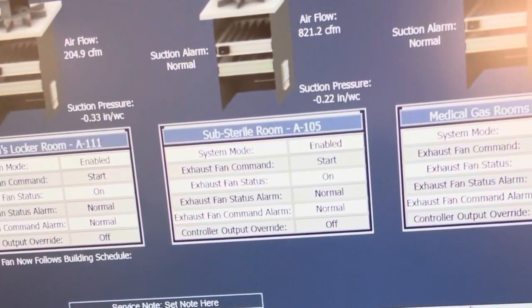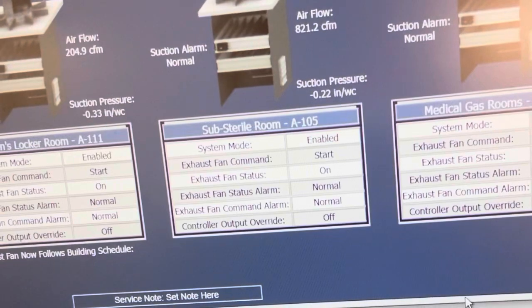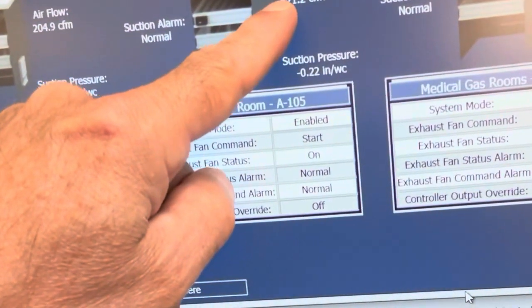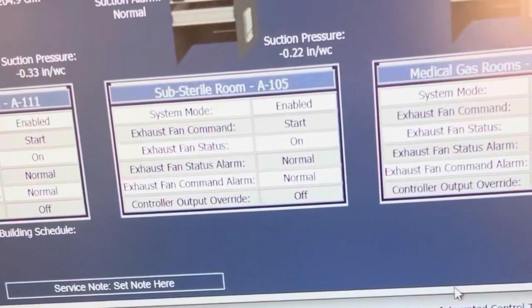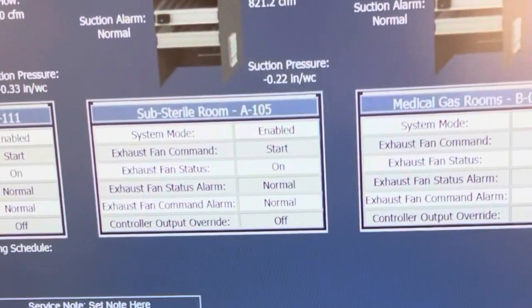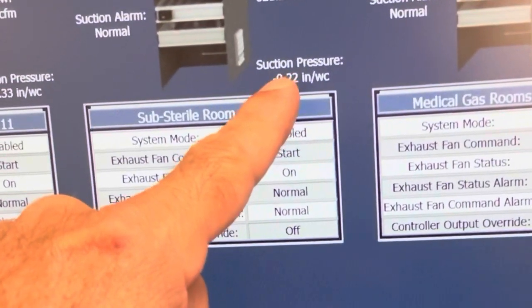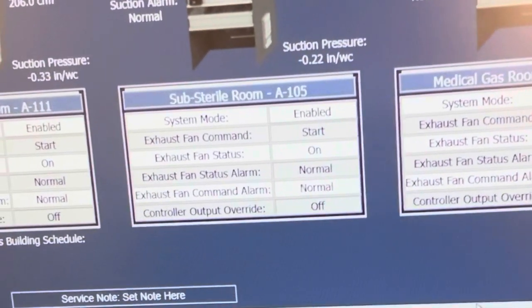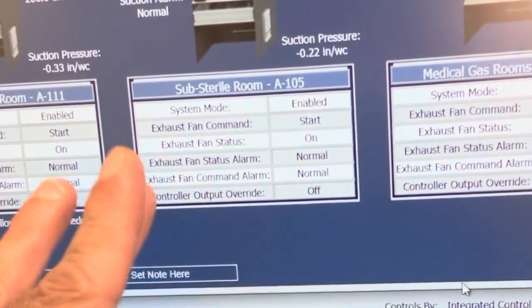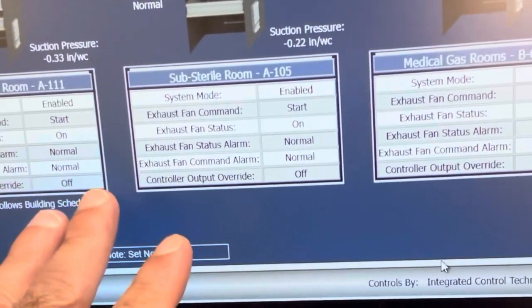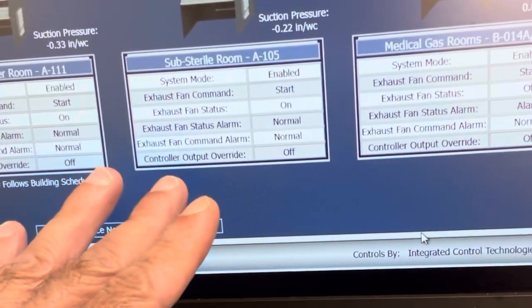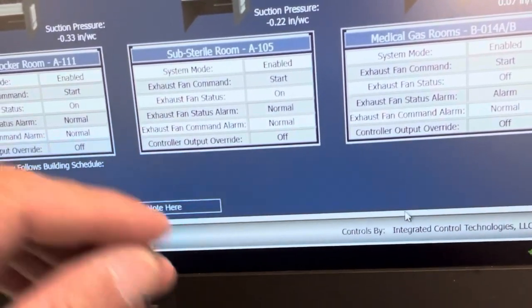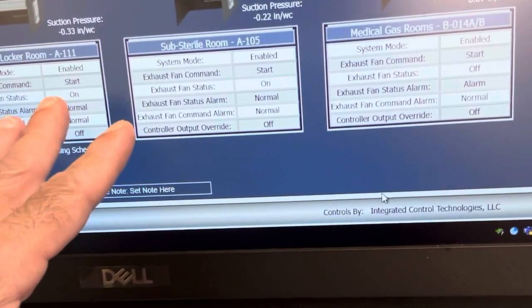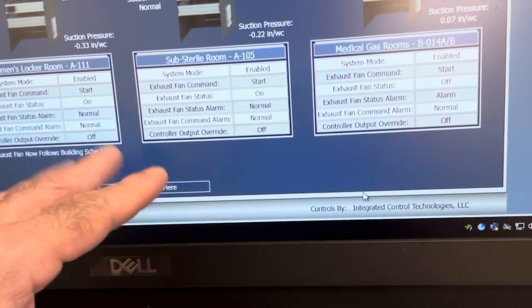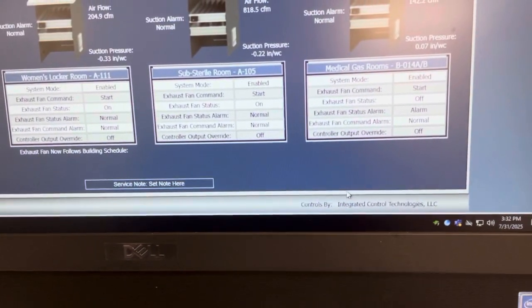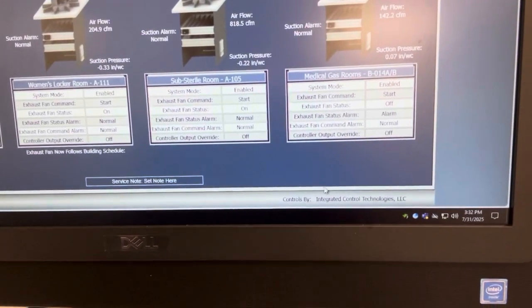So I think when I initially looked at it, the very first time, we were around 750. You can back up the video and see. So I increased it some, and now we're at a negative 0.22 in the ductwork. So evidently there's an alarm threshold. We have to be in a certain parameter, otherwise you get an alarm, and then it needs to be checked out, to see if there's a restriction or a problem with the motor or whatever. But this is all cleared up. I'm very happy to say.